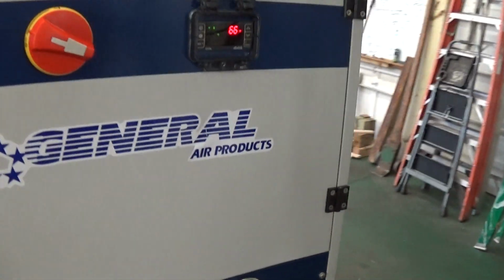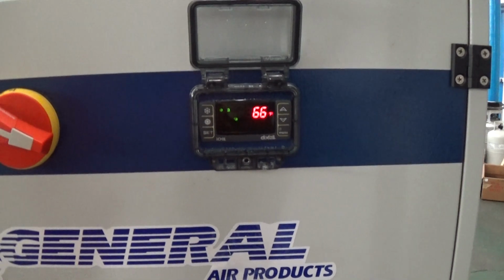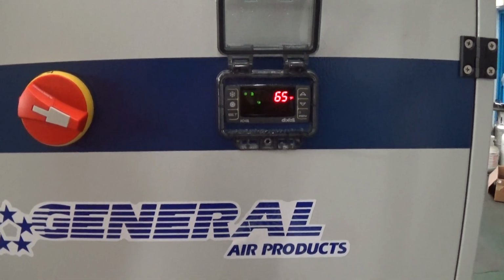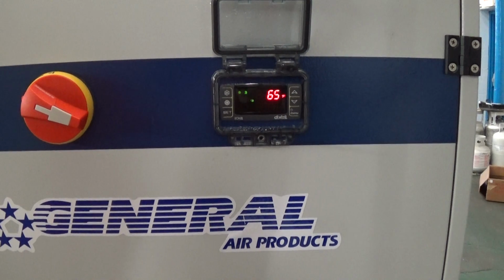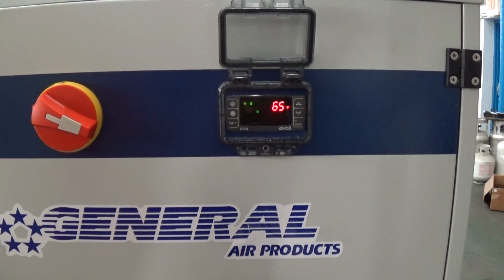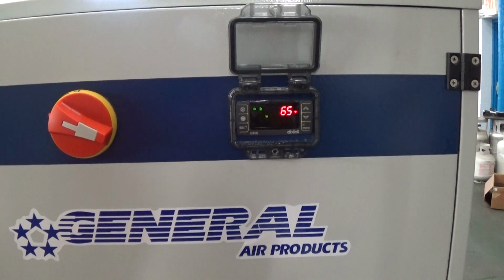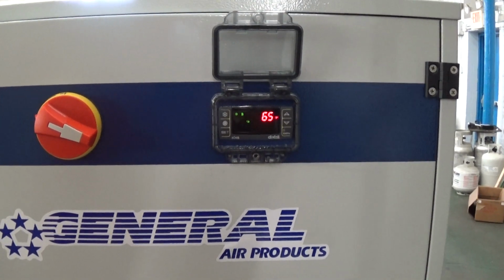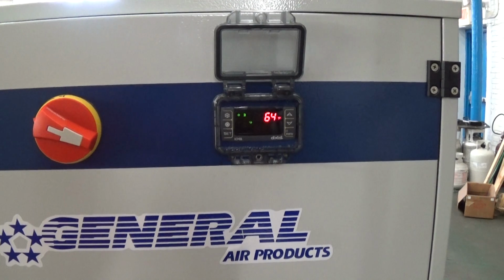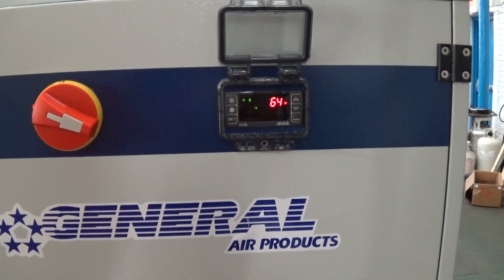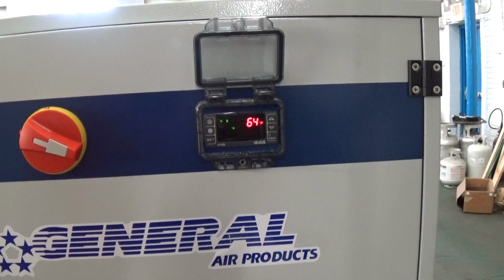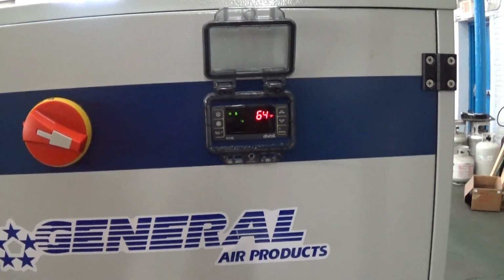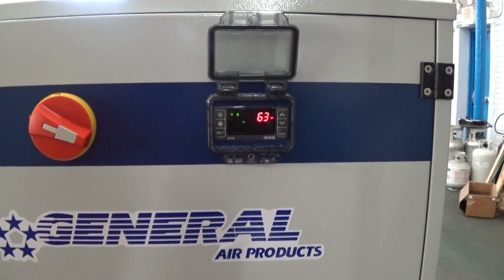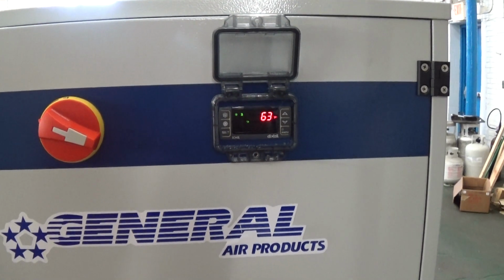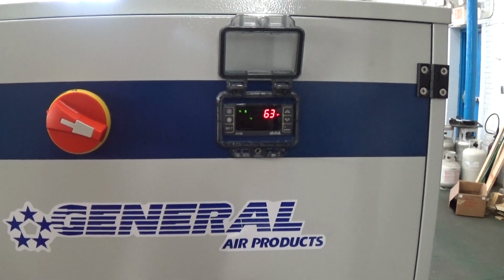This has a differential of about 4 degrees. You want to keep that, meaning it's going to run down to 20 F. The compressor and/or fans will shut off, and then it's going to wait till it gets up to 24 F to turn back on again. You don't want to run much tighter of a differential than that, because then you'll have short cycling of the compressor. We'll come back with video number 2 after we have this thing cycling on and off at the 20 F glycol temperature for a while. And when we do that, you'll actually see ice built up on the back fittings that I just showed you.